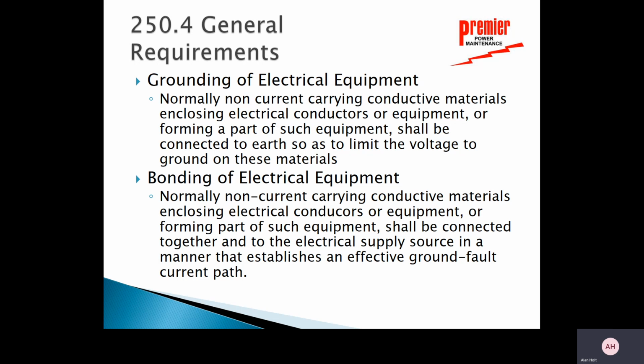Now, in that same section, 250.4, grounding of electrical equipment. Normally non-current carrying conductors, materials, and enclosures that are part of such equipment need to be connected to earth so as to limit the voltage to ground on these materials. So it can't be a situation where you come up and touch an electrical box and be shocked there. It's got to go to ground, okay? In the old days when we had two-wire electrical systems and no ground going to the washer, a lot of times we had washers or dryers, gas dryers, where you could actually touch the case of the washer or the dryer and get a little tingle there. That was because it was not effectively grounded.